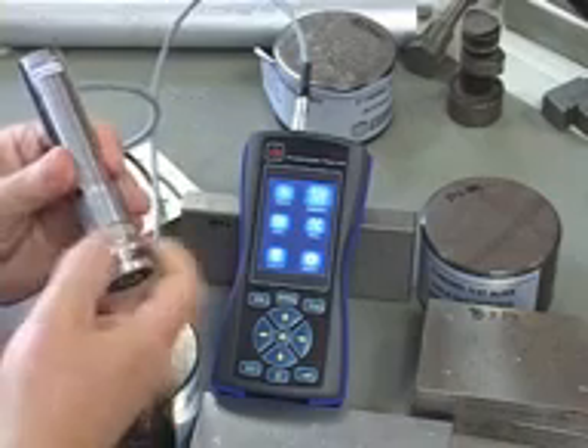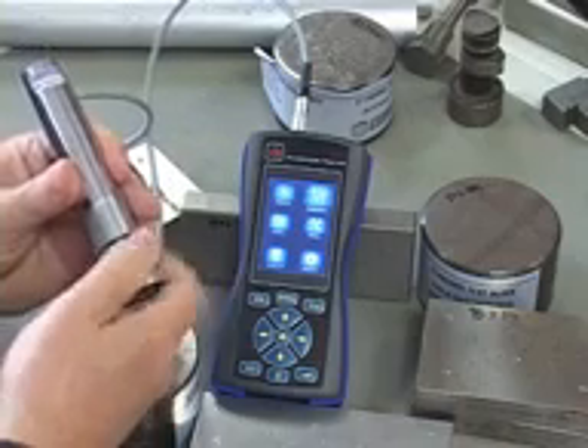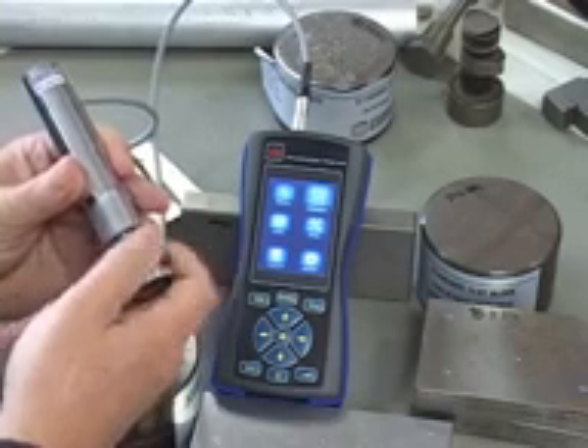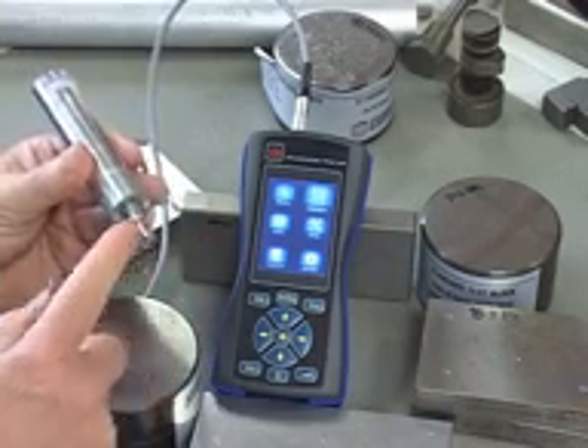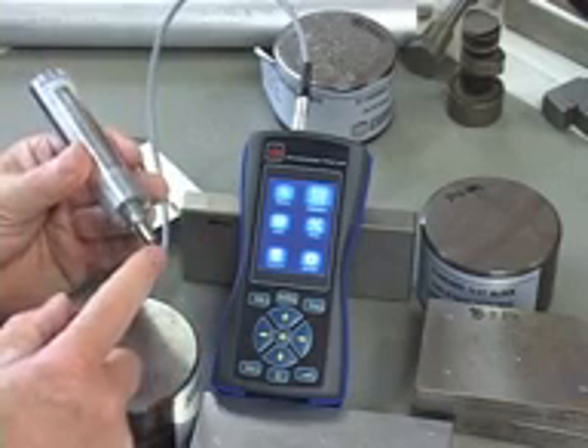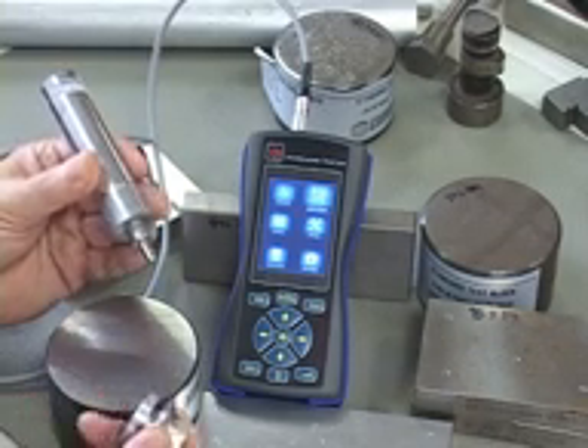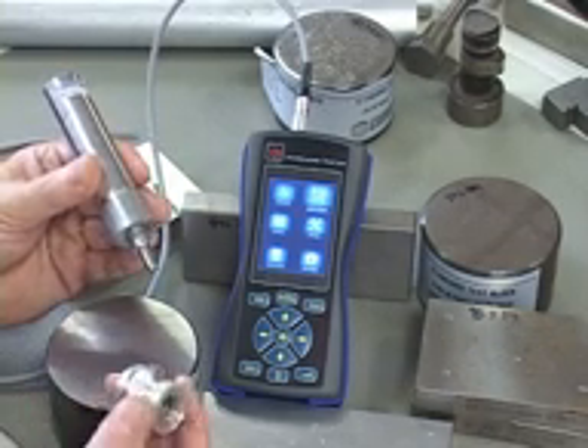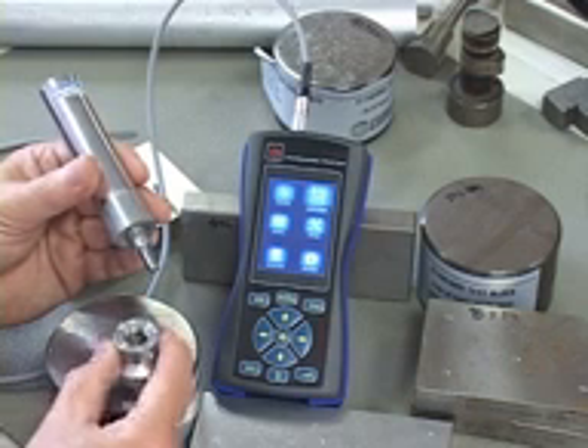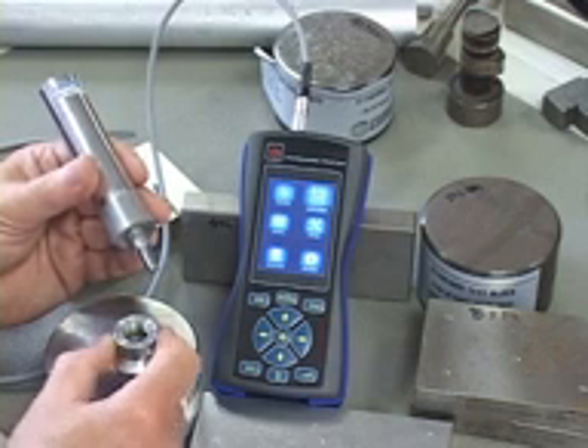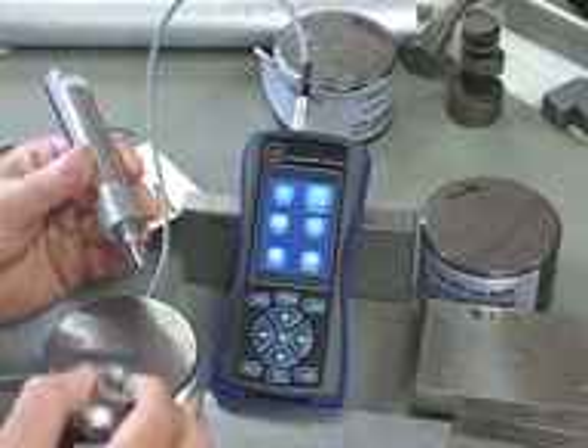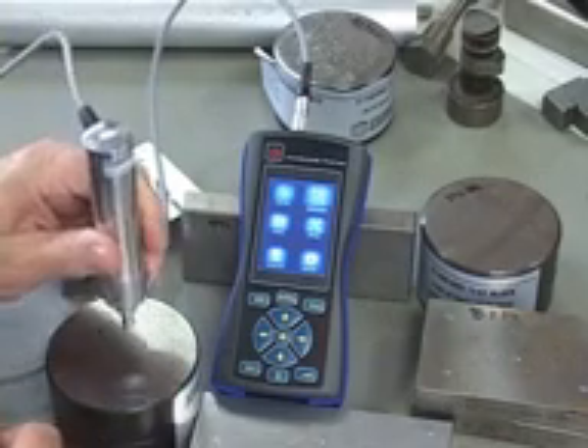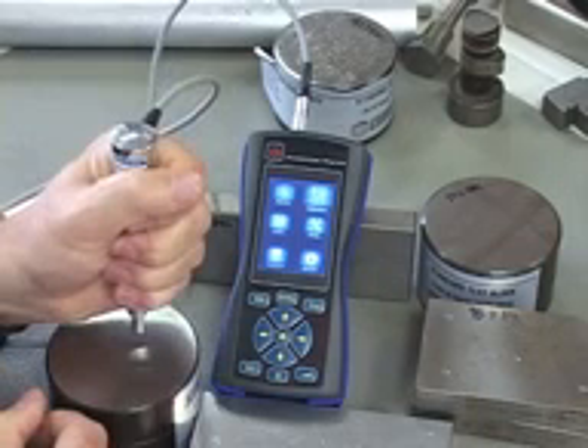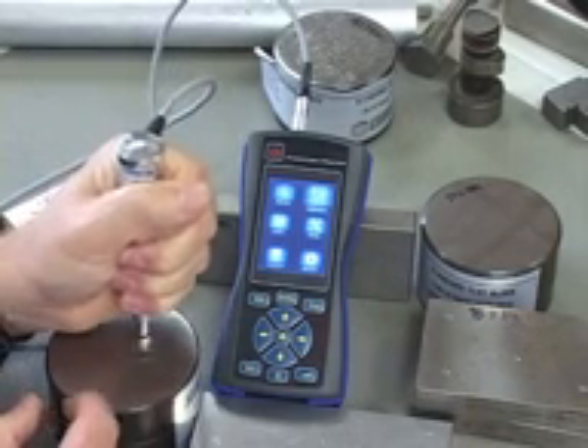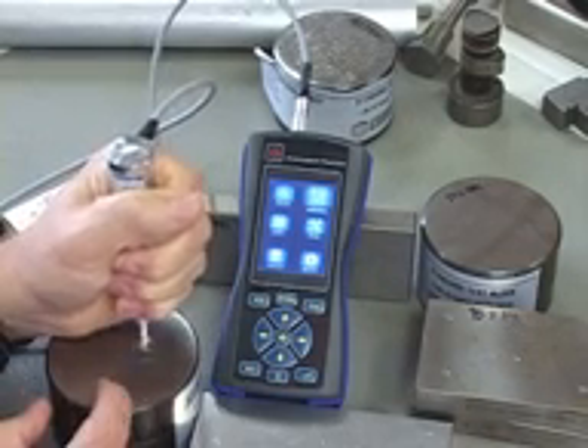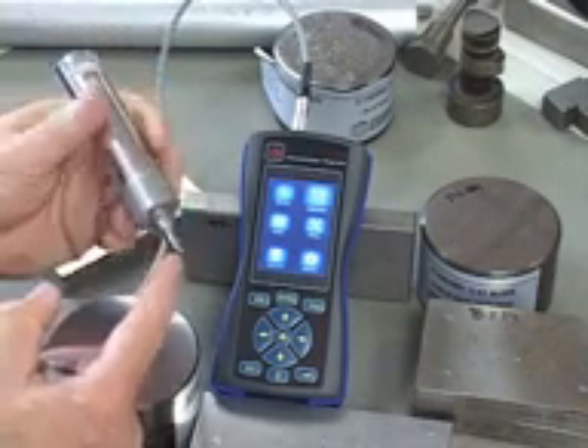So if I screw this off, we can see on the end of the probe, hidden here by the shroud, is the diamond tip. And the reason I'm showing you this is there's actually two parts to doing a test. It's all one fluid motion. The first one is the resistance, that is the spring in the puck to press down. And then the second resistance is actually when the diamond tip contacts the part, and it's the second motion, very short, to actually bottom out on the face of the probe itself.